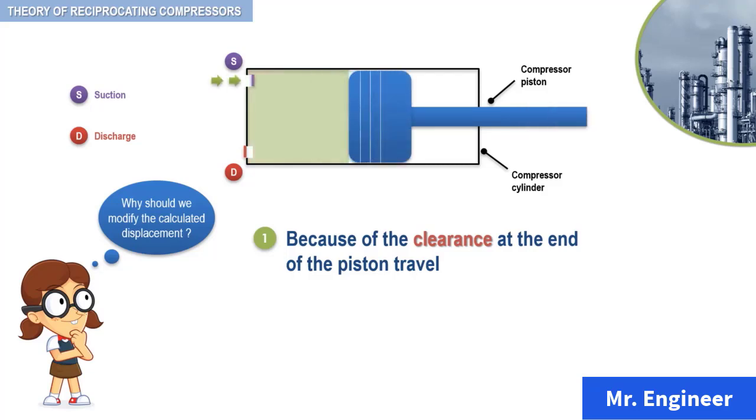The following equation reflects the expansion effect on capacity and is referred to as the theoretical volumetric efficiency. Here, F is the ratio of discharge compressibility to inlet compressibility. Rp is the pressure ratio.